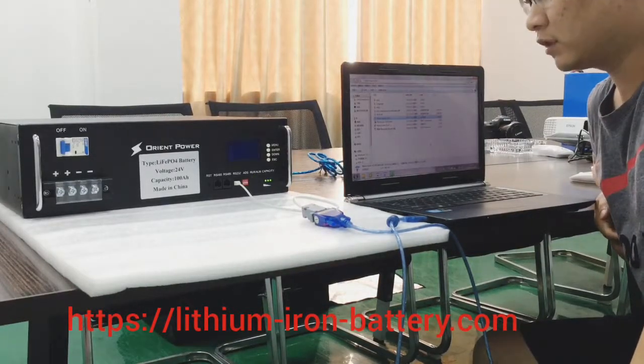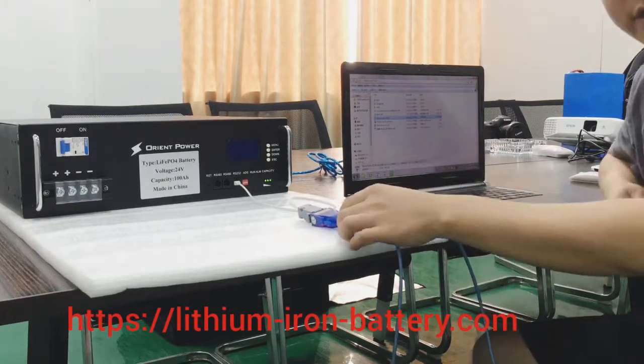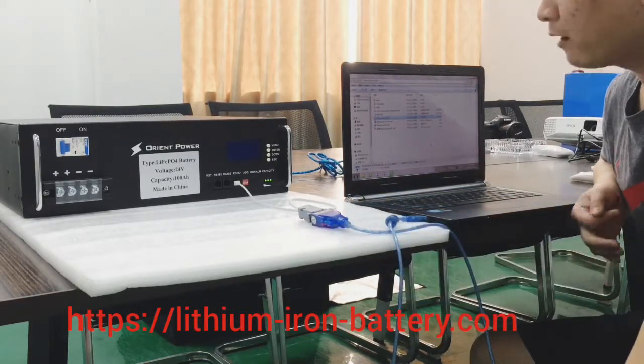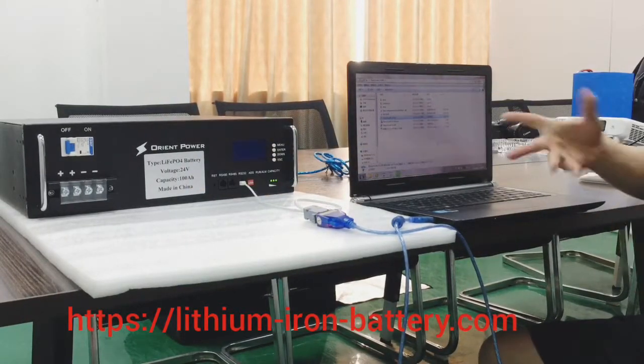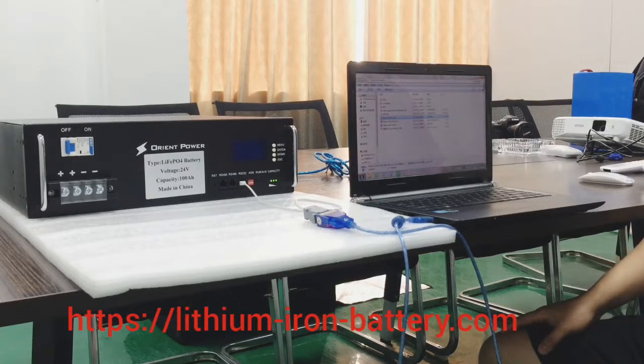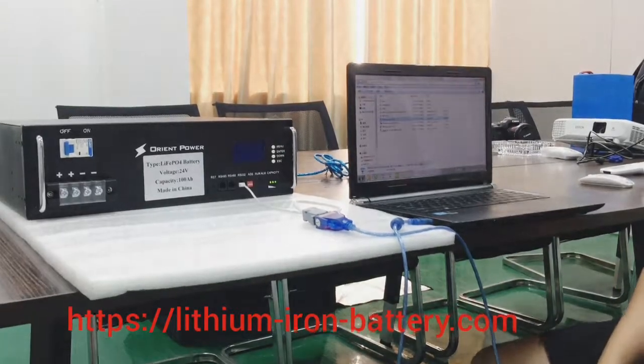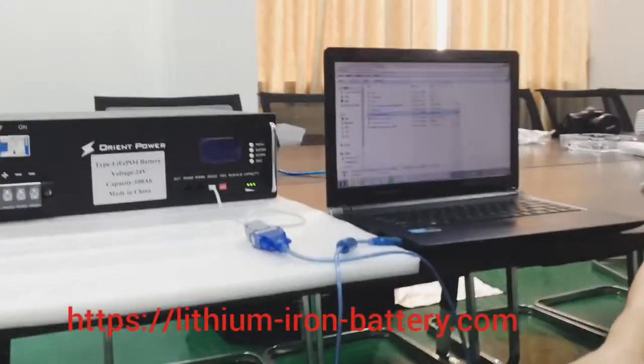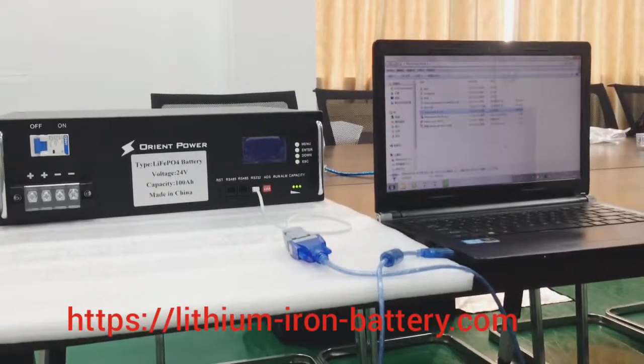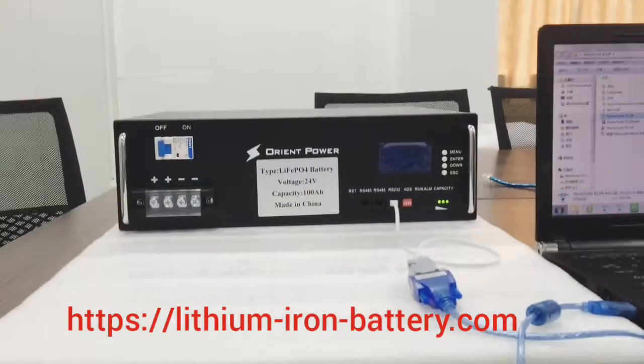Thank you for watching my video. This video is trying to show you how to connect the communication cable with our 24 volts 100 amp-hour lithium batteries to check the BMS data and the condition of this battery. This battery pack is made by 8 cells of 3.2 volts 100 amps lithium iron phosphate prismatic batteries.